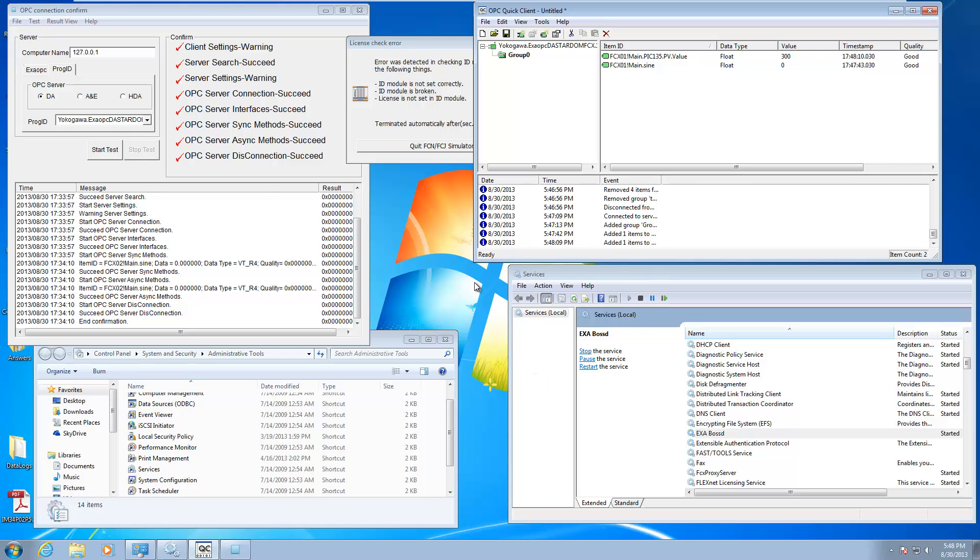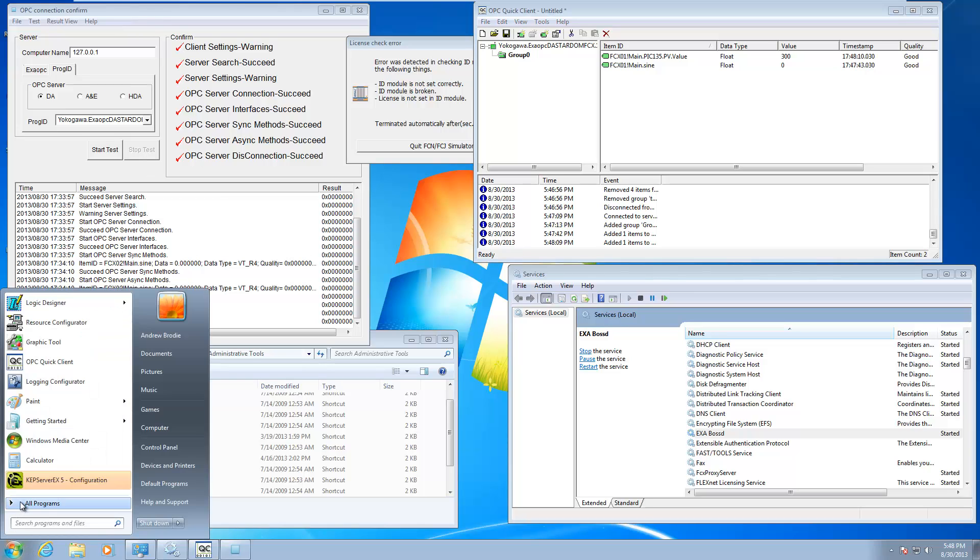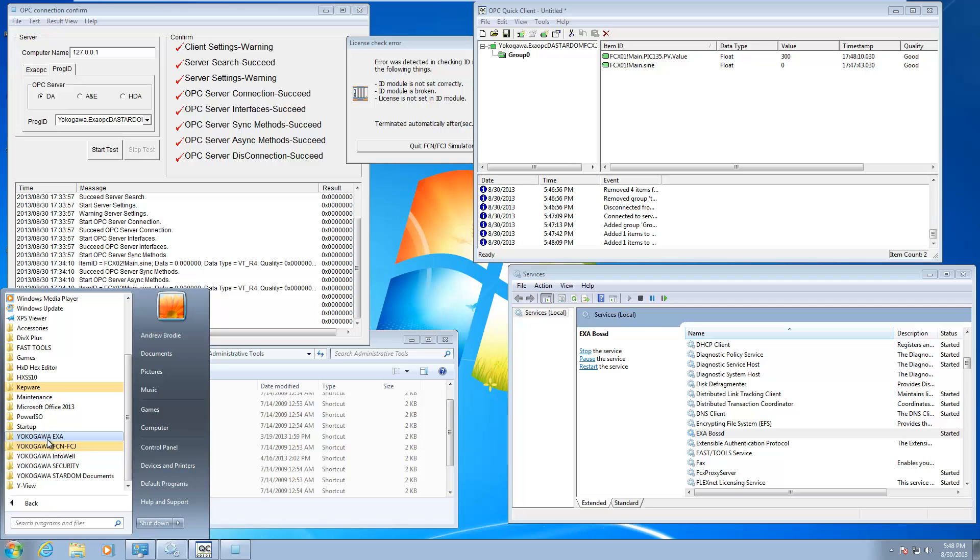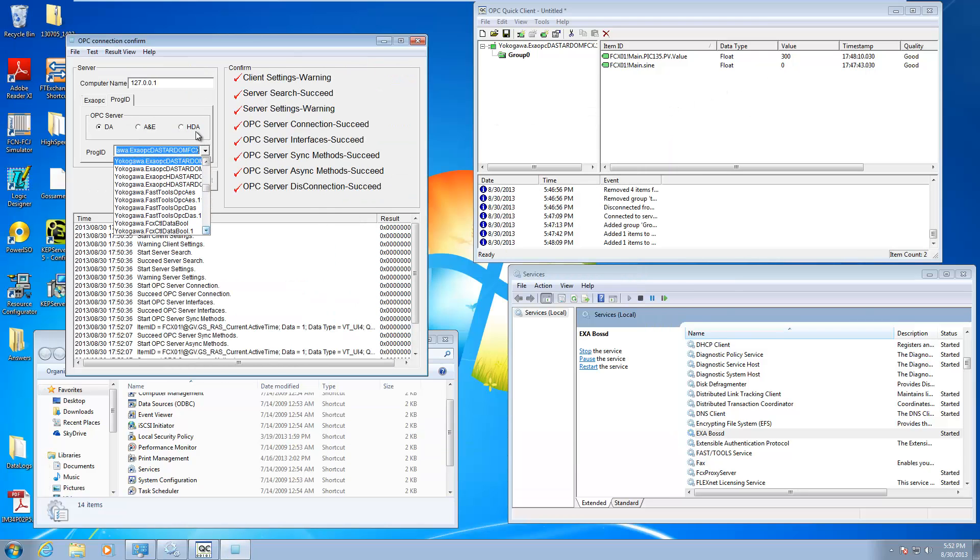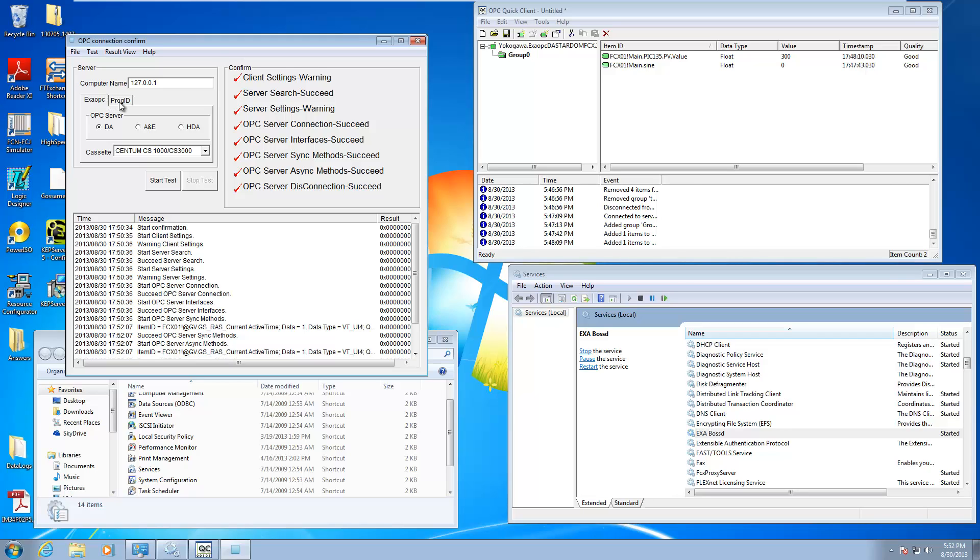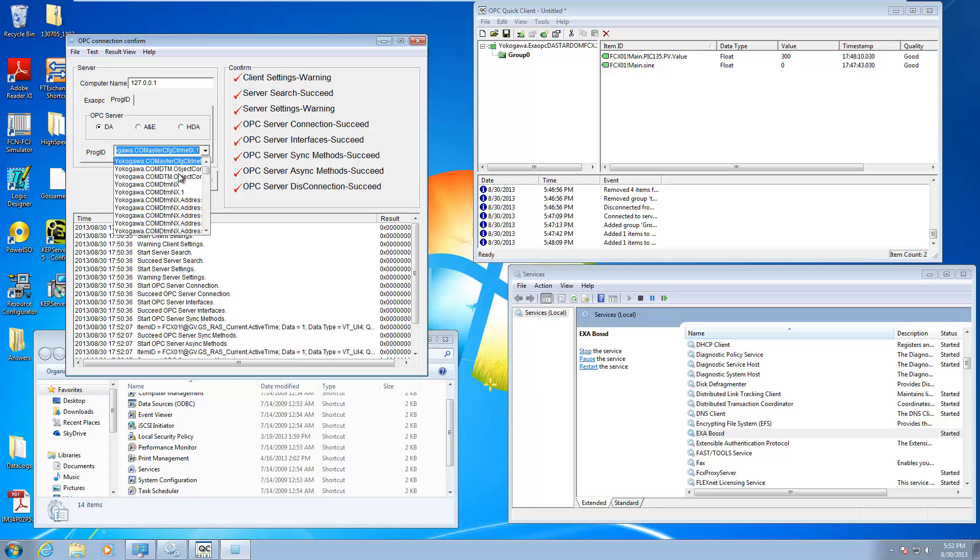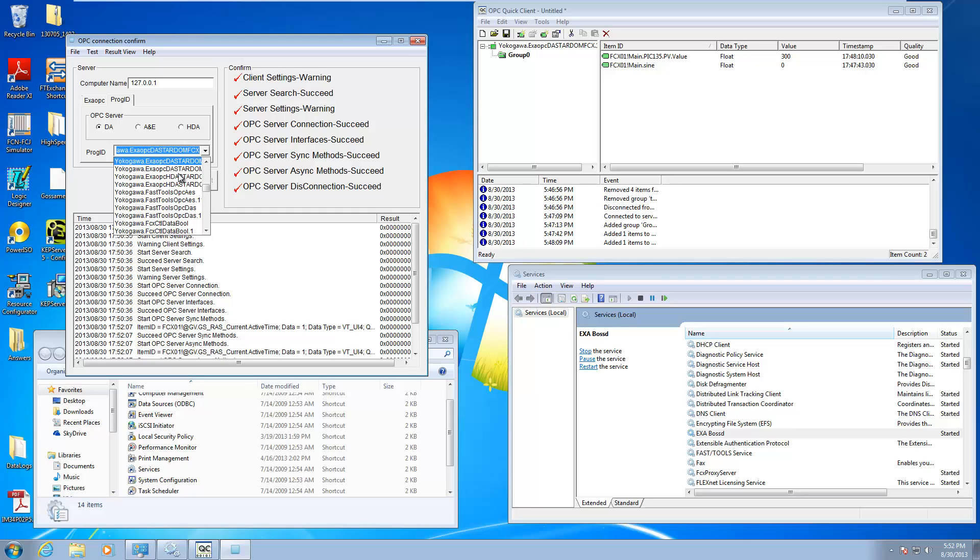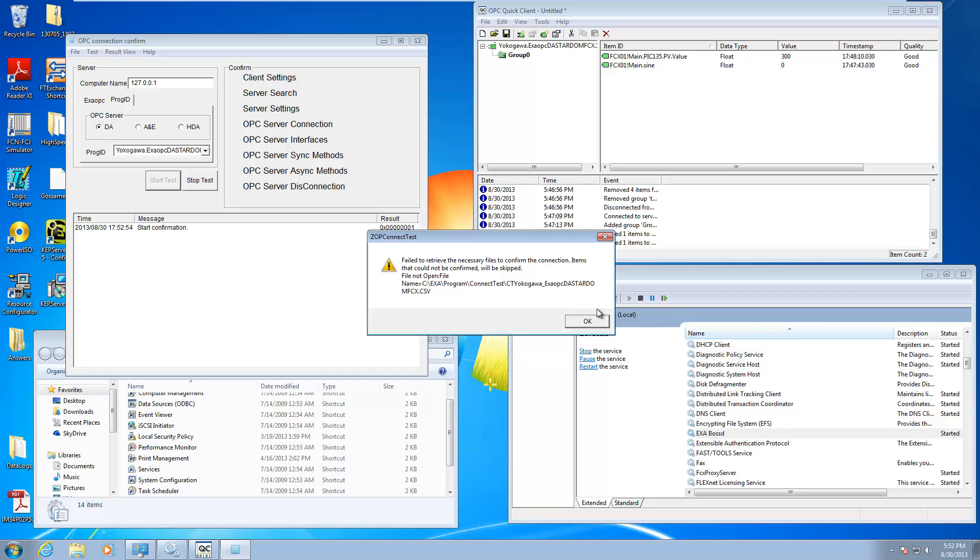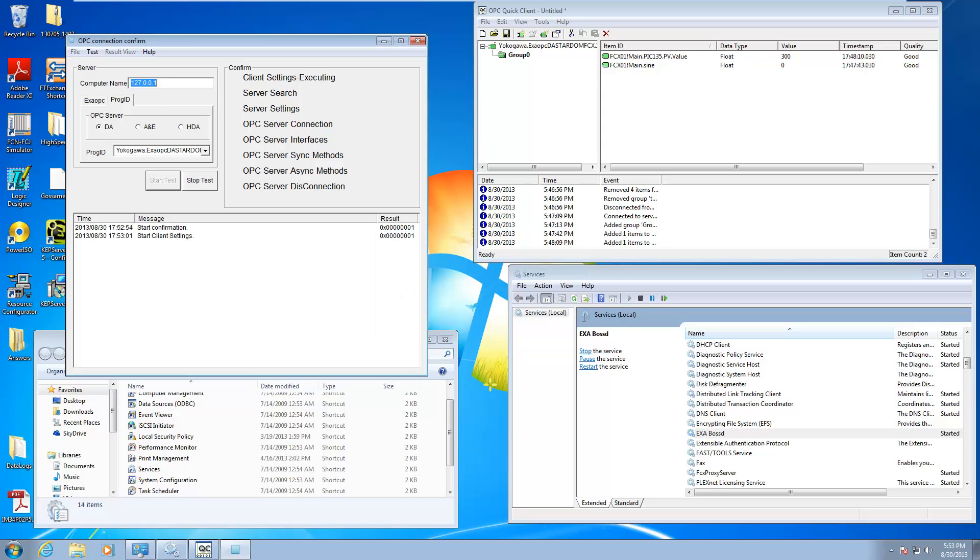There's another tool, if you don't have the OPC quick client, that you could kind of do a quick check on to see if your OPC is up and running with Stardom. And it's this OPC connection confirm tool. That's start all programs, Yokogawa EXA, right here, OPC connection confirm. You're going to want to open it up. It's going to start on the EXA OPC tab, go to the PROG ID tab, make sure DA is selected. And then if you just kind of scroll down, they're a little long right now, but you're going to look for something that says Yokogawa EXA DA Stardom FCX. Then you're going to go ahead and do a start on that.